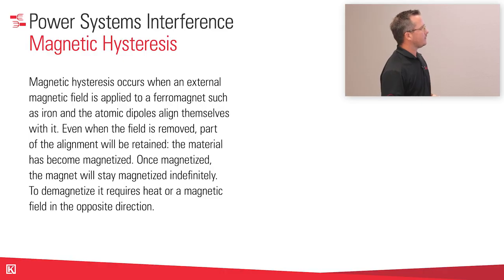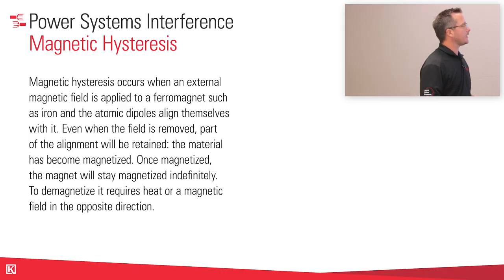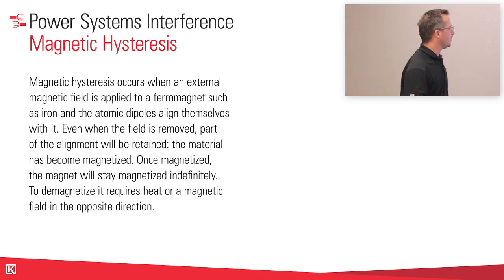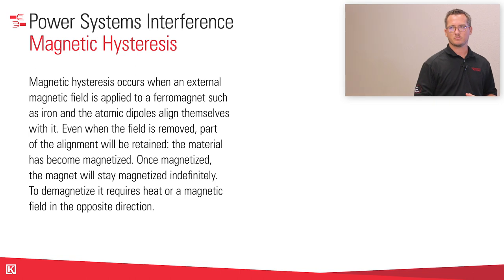With magnetic interference, you also have magnetic hysteresis issues. So when you have a big iron tank, a big steel compressor sitting on a gravel pad, if it's not grounded or bonded and it becomes magnetized, that'll create a lot of false readings. So you're going to either need to reverse the magnetism or have a route for it to dissipate on its own.